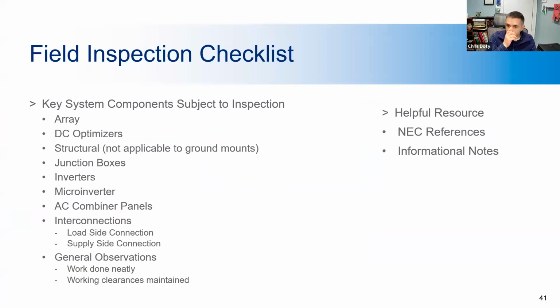Okay. So this field inspection checklist provides an organized method of review. You would start at one end of the system and go to the other. You can either start at the array and go to the interconnection, or you can start at the interconnection and go to the array. It doesn't really matter how you do it, as long as you do it consistently. And this will help you move through quickly each time and not make errors if you do it the same way each time, right? The more times you do it, the better you'll get at it, and the fewer errors you'll make. And so we're going to go through a run through of the basic items covered in the checklist. And let's jump in.